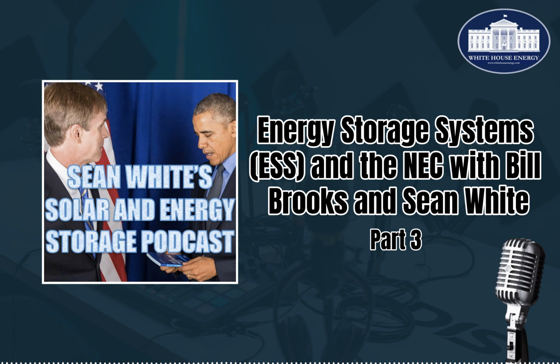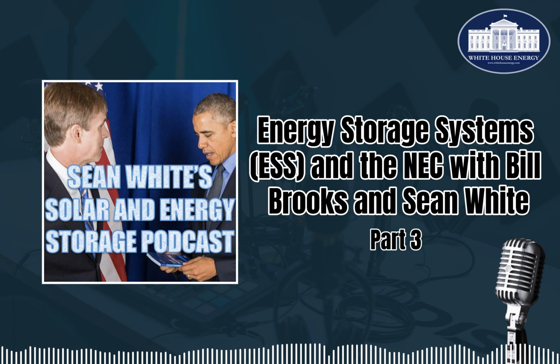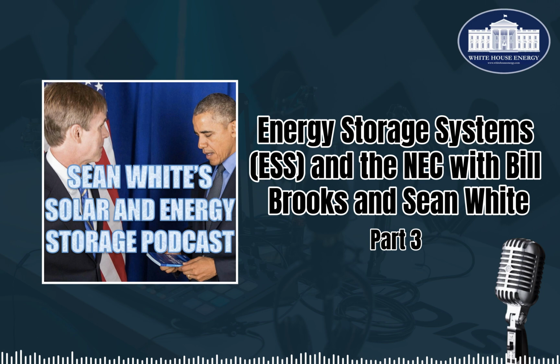But to say that my PV system connected to an energy storage system, both operating at 400 volts, going into, say, a SolarEdge inverter or something like that, is a DC microgrid is absolutely false. There's no DC microgrid controller. There's none of that stuff. Do not go into Article 712 for the typical equipment that's on the market today. That's all covered under 705.